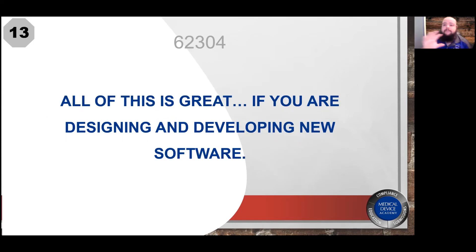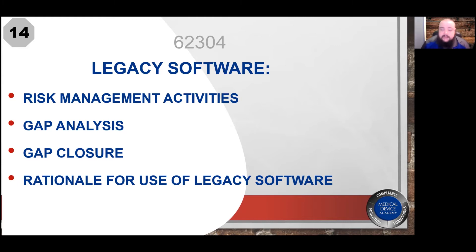All of that is fantastic if you are currently developing new software. The good news is the standard also has contingencies for the use of legacy software. If you have legacy software, the standard has requirements for the additional risk management activities you have to perform, what gap analysis you have to conduct, and you'll need to close those gaps and provide a rationale for the use of your legacy software. Legacy software is addressed within the standard.